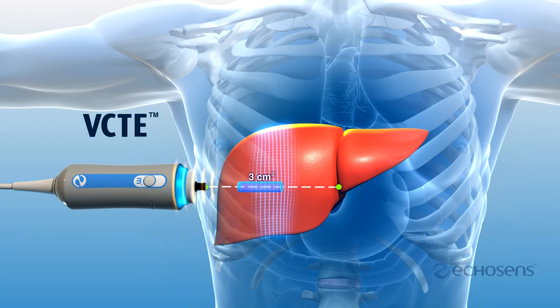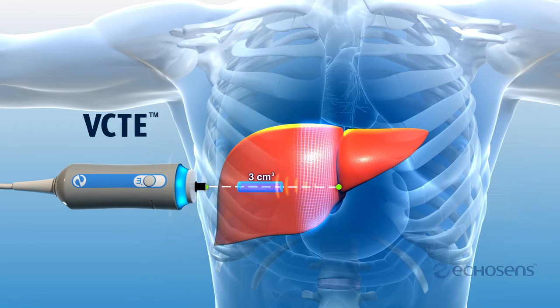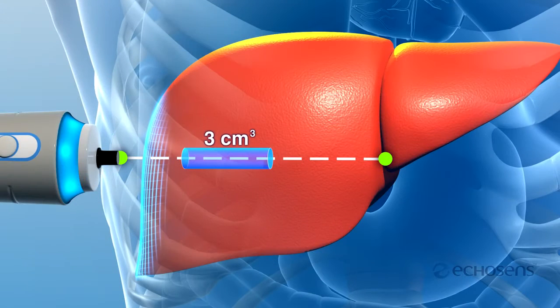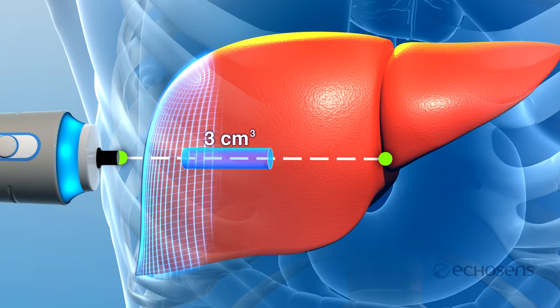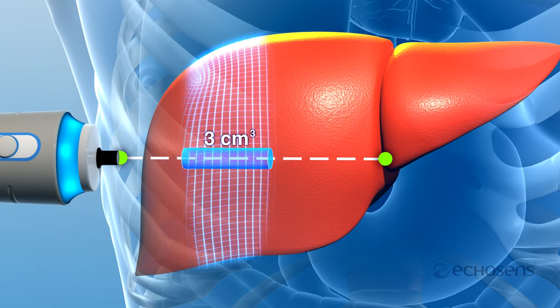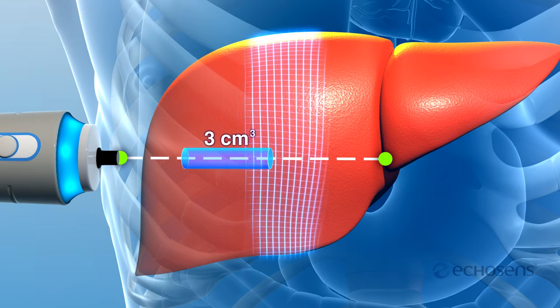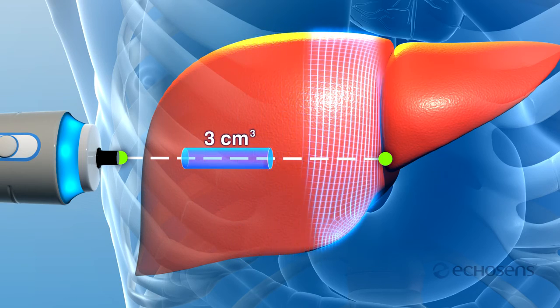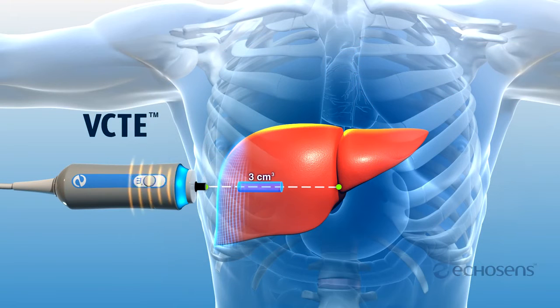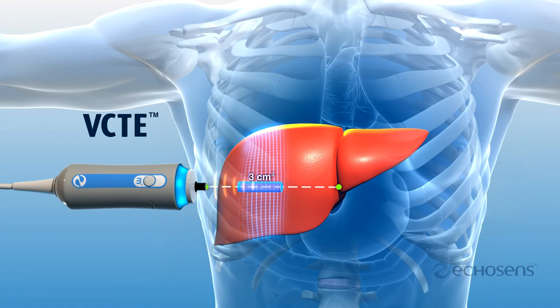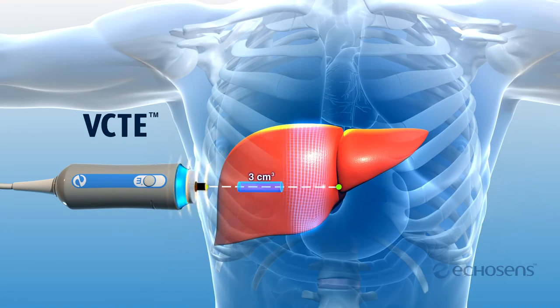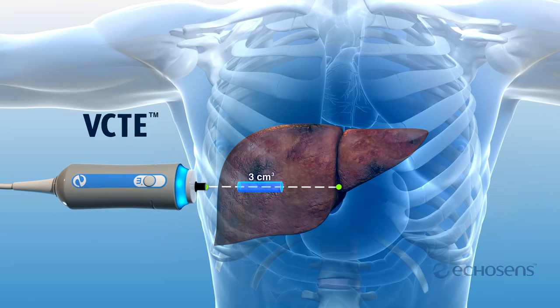The mechanical shear wave travels through the liver tissue. The shear wave's speed is measured by ultrasound pulses which reflect off the wave as it passes through the 3 cubic centimeter exam cylinder. The speed of the shear wave is used to calculate liver stiffness, reported in kilopascals. Here, the shear wave moves slowly through a healthy liver. In a cirrhotic liver, the shear wave moves very rapidly.